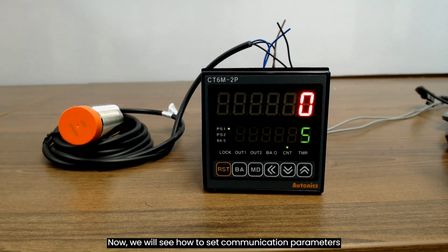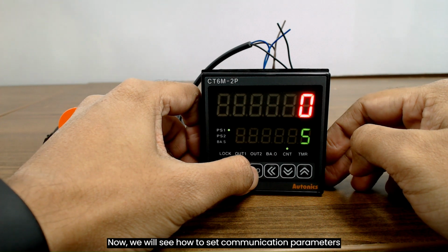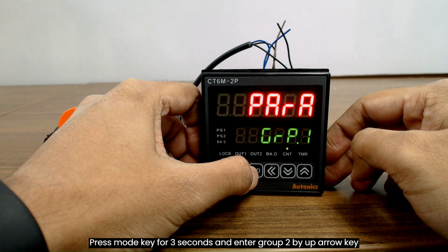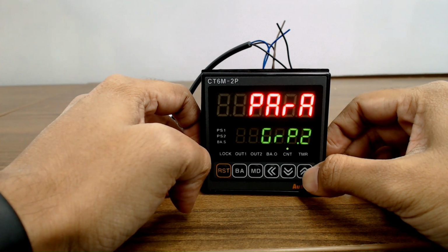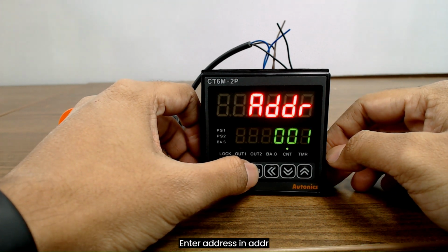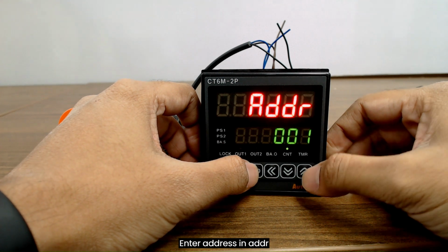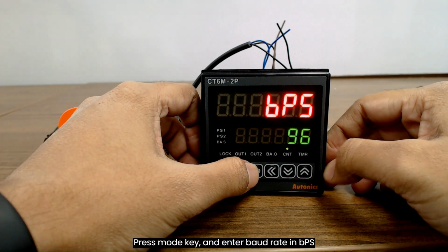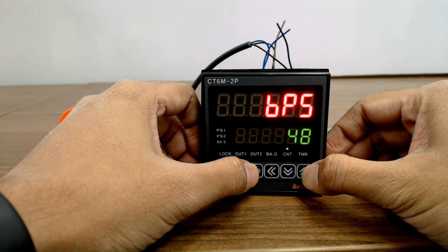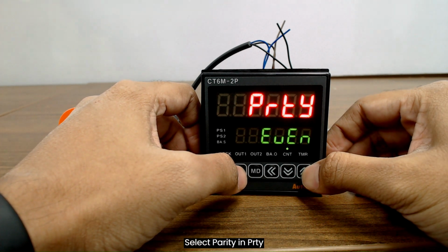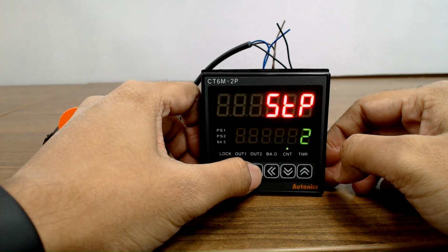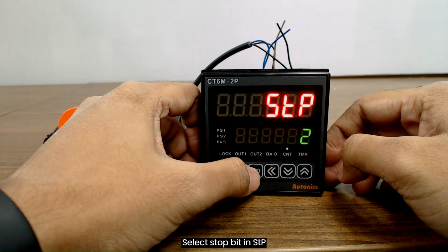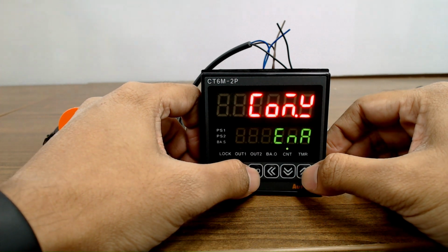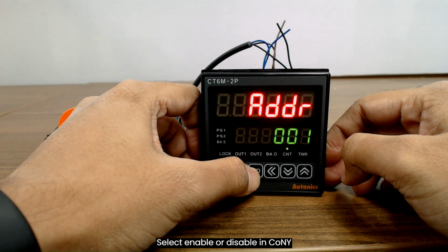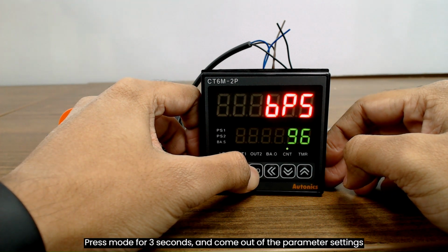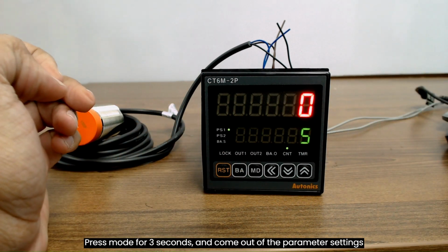Now, we will see how to set the communication parameters. Press mode key for 3 seconds and enter group 2 by up-down arrow key. Enter address in ADDR. Press mode key and enter the baud rate in BPS. Select parity in PRTY. Select stop bit in STP. Select enable or disable in CONY. Press mode for 3 seconds and come out of the parameter settings.